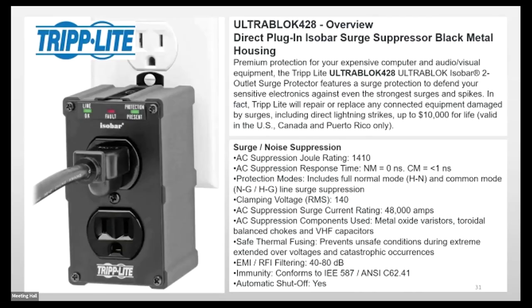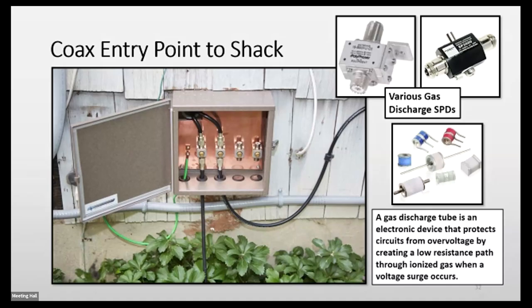Okay, coax entry point. So how do you protect that coax coming in? Nice if you can do this on the outside of your house. There's various gas discharge SPDs, or surge protection devices. The little box in the middle on the right, that's the elements inside of it. Afterwards, if you want to come up and see what the little device inside looks like after it's been hit by lightning, I got 3 brand new ones here you can look at. I'll leave it on the table rather than pass it around. And if you want to go deeper, you can unscrew this one and still see the burn marks inside after the last lightning hit we took.